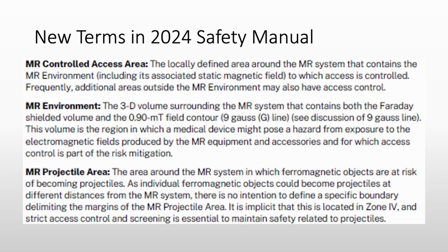Defining areas, zones, and environments located within the MRI safety zones helps lend clarity to the rationale for organizing the MRI facility into 4 zones. In the past, we have only spoken about the 4 safety zones, zones 1 through 4. But these safety zones are based upon the MRI areas noted here. Controlled access areas are those areas that include the MRI environment, but also are areas that need to be controlled to prevent access to MRI Zone 4. The MRI environment is the 3D volume around the magnetic field that contains the Faraday shielded volume, which is the MRI room, but also contains the 9 Gauss line. This is the area where medical devices can be impacted. Note the change in the MRI environment area from the 5 Gauss line to now the 9 Gauss line. We have also clearly identified the new MRI projectile area, which is fairly self-explanatory. Based on these areas and environments, the MRI facility may be conceptually divided into 4 zones for MRI safety purposes.